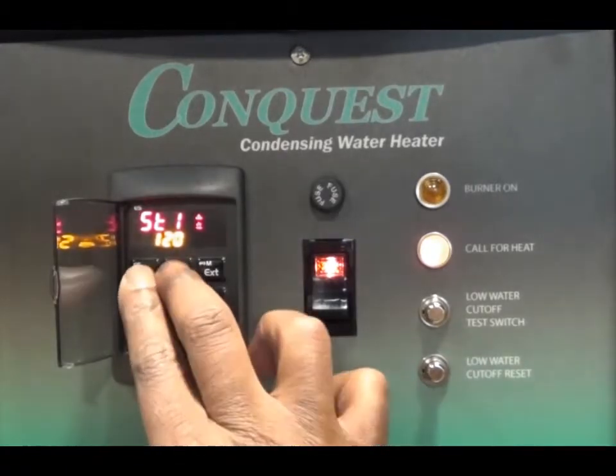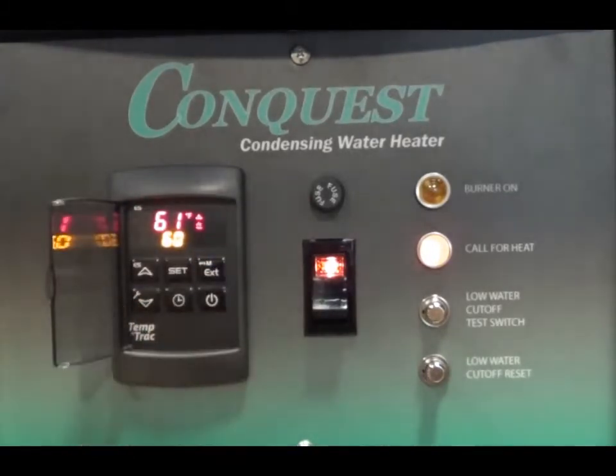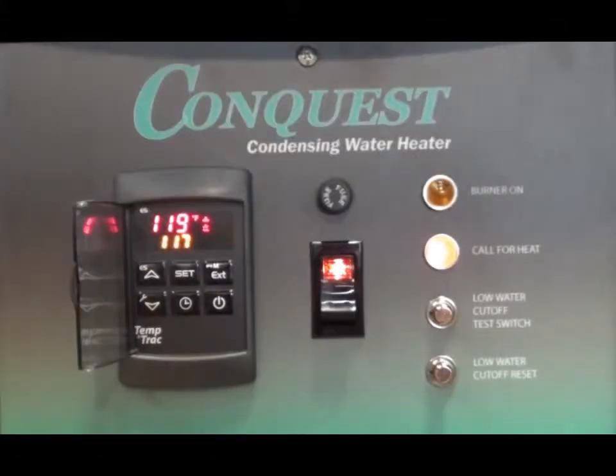Following a 30-second pre-purge and 20-second hot surface igniter heat-up period, trial for ignition is initiated. The burner on light on the control panel will illuminate when the trial for ignition begins. With no gas pressure, flame will not be established and the ignition control will attempt 2 more trials for ignition before locking out. The 3 tries for ignition prior to lockout will take about 5 to 7 minutes.